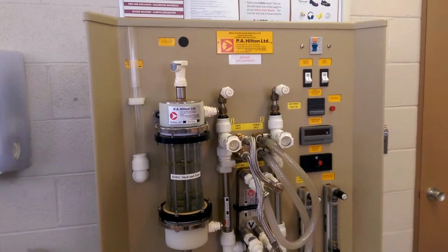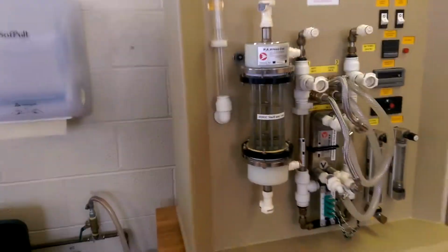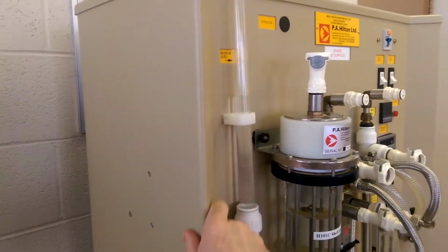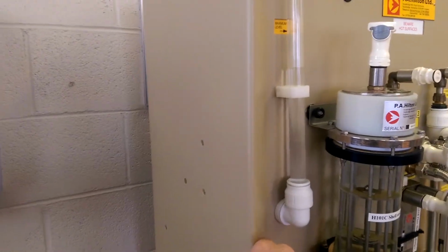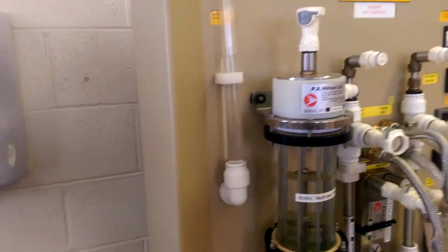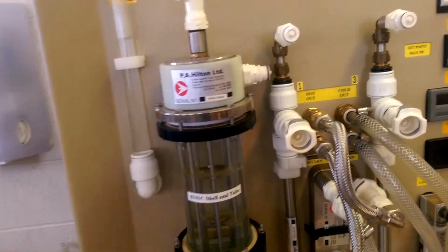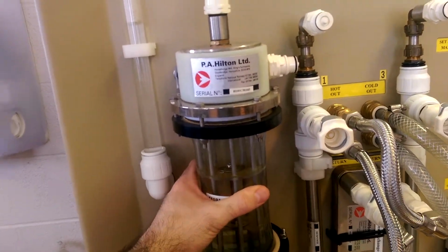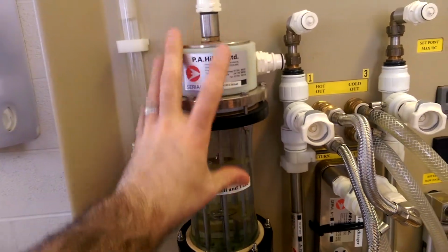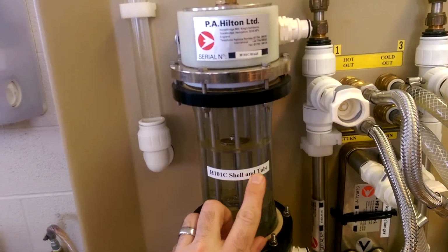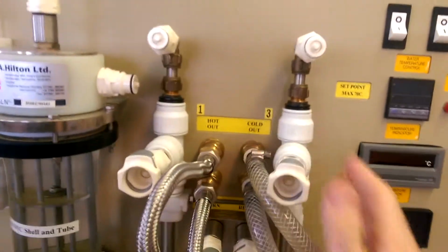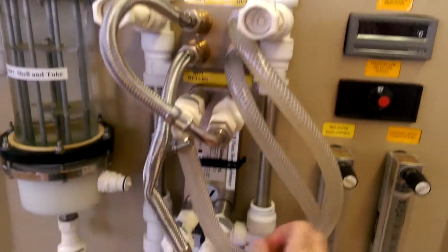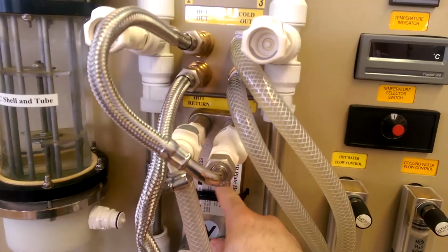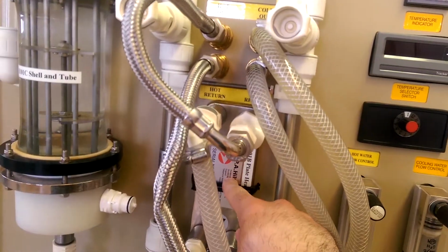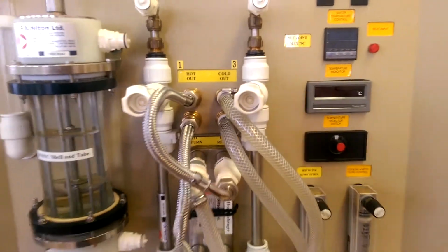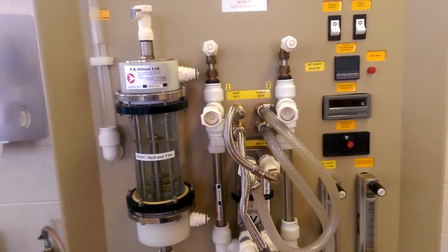First, I want to mention that people tend to think this tan box unit is the heat exchanger. That is incorrect. The heat exchangers are actually attached to the front-facing panel of this box. This right here is a miniaturized version of a shell and tube heat exchanger. This is a double pipe heat exchanger, and in the middle, attached to the front face, is a plate heat exchanger. So there are three different heat exchangers.